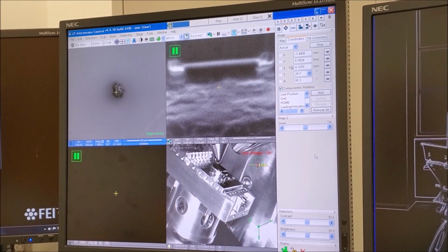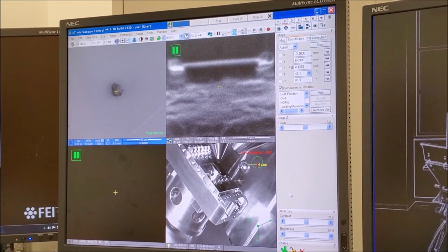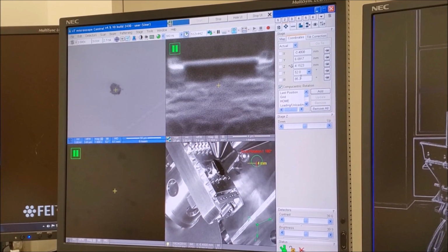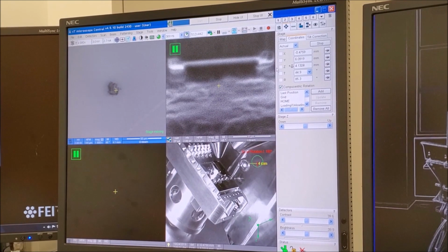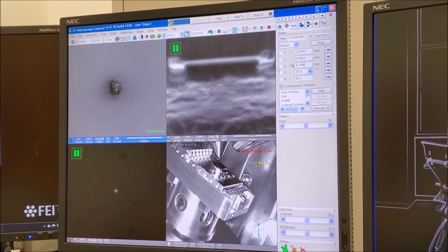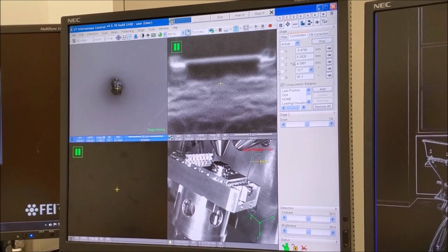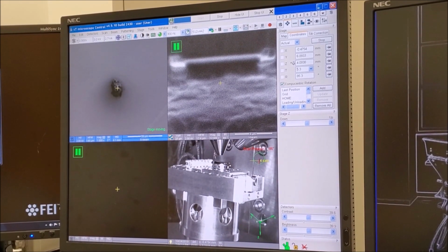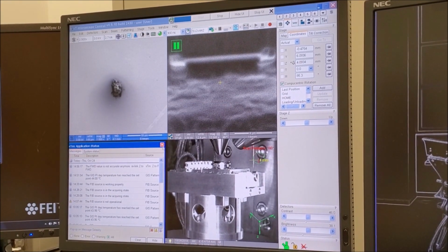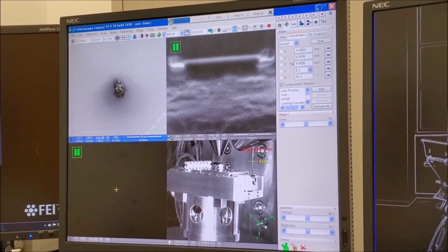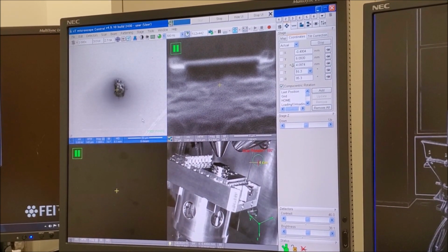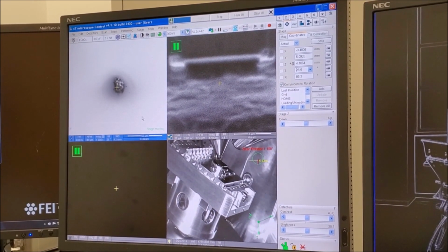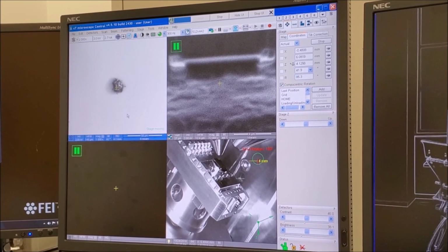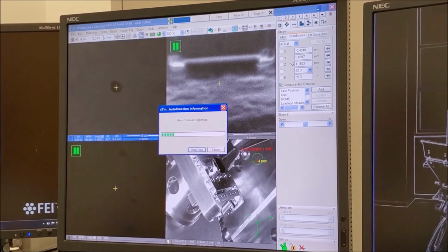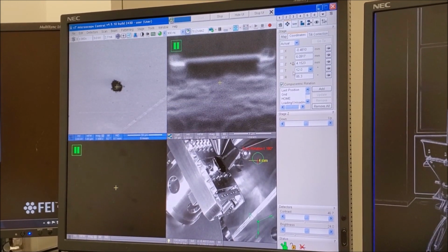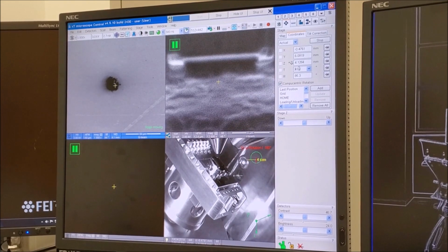Then increase the stage tilt to 52 degrees, again noting if any movement of the feature from the center of the image occurs. Should there be any when the tilt is completed, once again use the stage Z control to return the feature to the center of the image. Then return the stage tilt back to 0 degrees. Recenter the feature in the image and then change the stage tilt to 52 degrees. Note any movement of the feature from the center of the image once tilting is done, and if any occurs, use the stage Z control to adjust the stage position accordingly so the feature goes back to the center of the image. Then return the stage tilt back to 0 degrees.